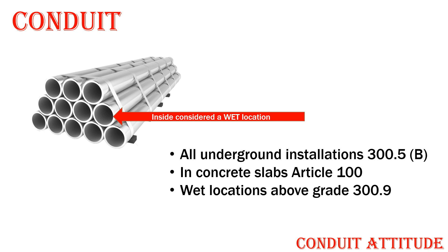The last place — and you may not think about this or may not even know about it — is inside of a wet location that is above grade. It does not matter where you are: if you're above grade and that conduit is installed in a wet location, then the inside of the conduit is considered a wet location. You have to use wet-rated wire, install fittings so they drain, and keep moisture from getting inside, just like you would in the pouring rain.